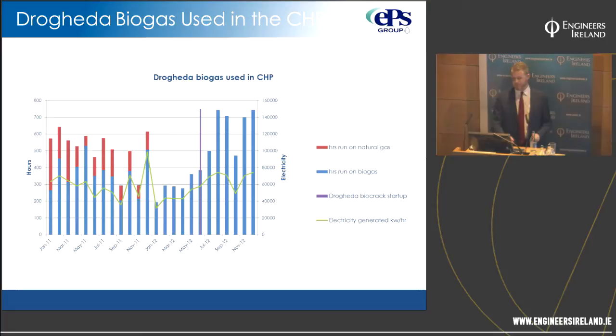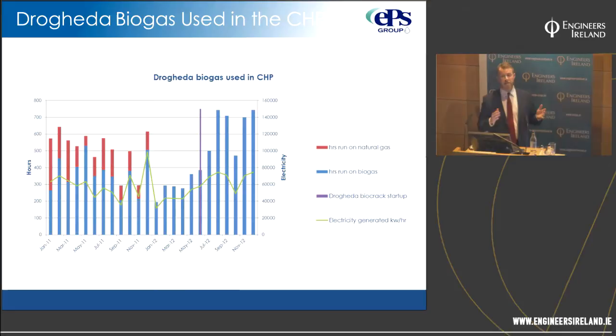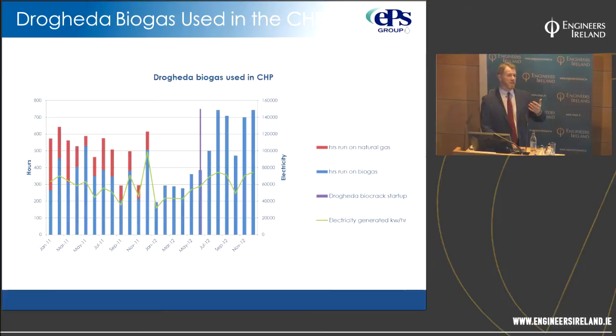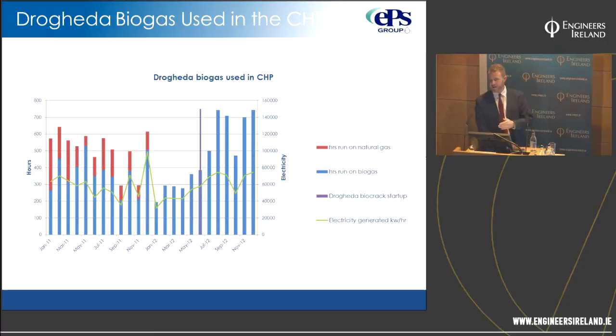Drogheda is the extremely significant one — we don't use natural gas on that site anymore. This comes back to the hydrolysis stage. The biodegradability of those cell walls is so significant. Drogheda had a 14-day sludge retention time during these trials; Dundalk was closer to 30 days due to volume. At 30 days, the process completes regardless of whether you improve it. But on a tighter 14-day timescale, the process hasn't completed fully, and BioCrack encourages it to do so — which is why you see the significant difference at Drogheda.